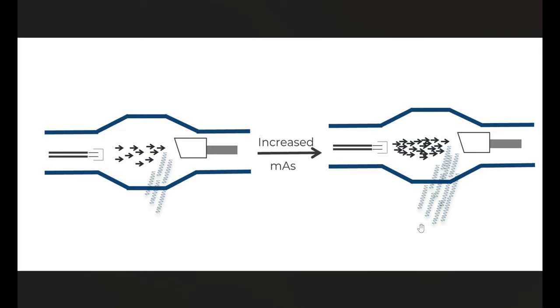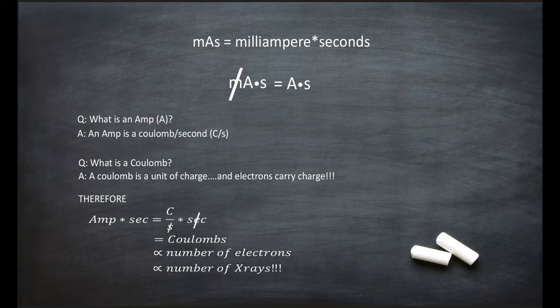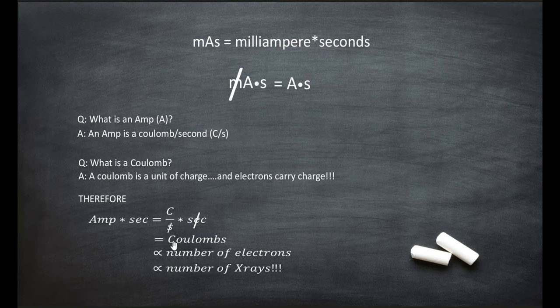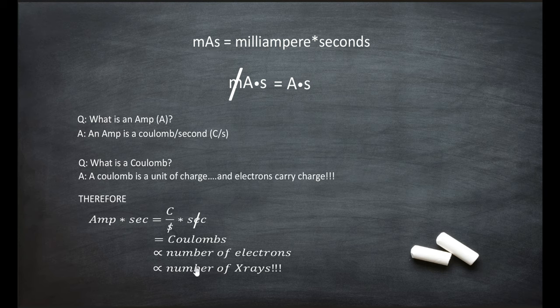mAs is a control that's directly proportional to radiation dose. If we double the mAs, we're going to double the radiation dose to the patient. mAs is milliampere times seconds. If we strip away the milli prefix, we're left with amps and seconds. An amp is a Coulomb per second. A Coulomb is a unit of charge, and we know that electrons carry charge. So amps times seconds is Coulombs per second times seconds — the seconds cancel and we're left with just Coulombs. Since Coulombs is a unit of charge and electrons carry charge, that's proportional to the number of electrons, which is proportional to the number of x-rays. This is how we go from mAs to the number of x-rays.